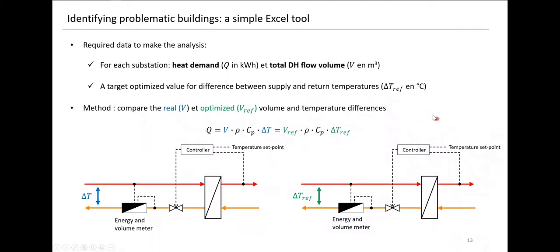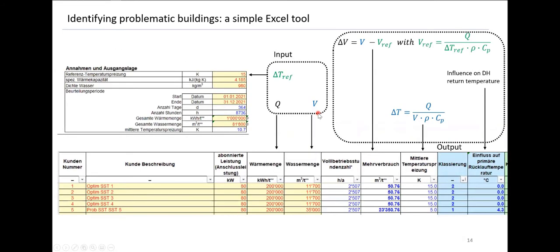To make the analysis, we need for each substation the consumed heat of the building — annual readings, for example — and the total volume that passes through the substation. You must also set a target value for your delta T, which we call delta T ref. The method is to compare the actual volume consumed by the substation with an optimized volume — the volume the substation would have consumed if it had reached the target delta T.